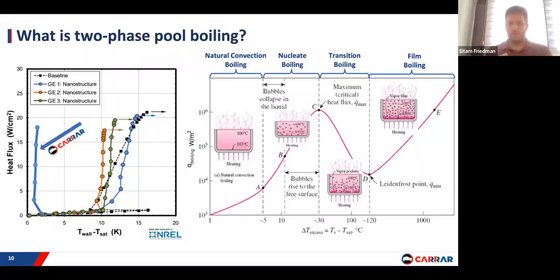They did a nanostructure coating on a copper plate, and managed to reduce this boiling incipience to 8 degrees. So let's say the boiling point we want for the battery is 25 degrees — we'd need the boiling point now at 17 degrees. If we have a refrigerant that boils at 25, we need to apply vacuum to bring it to 17 degrees, and then before the condenser, we need to increase the pressure back in order to condense it.